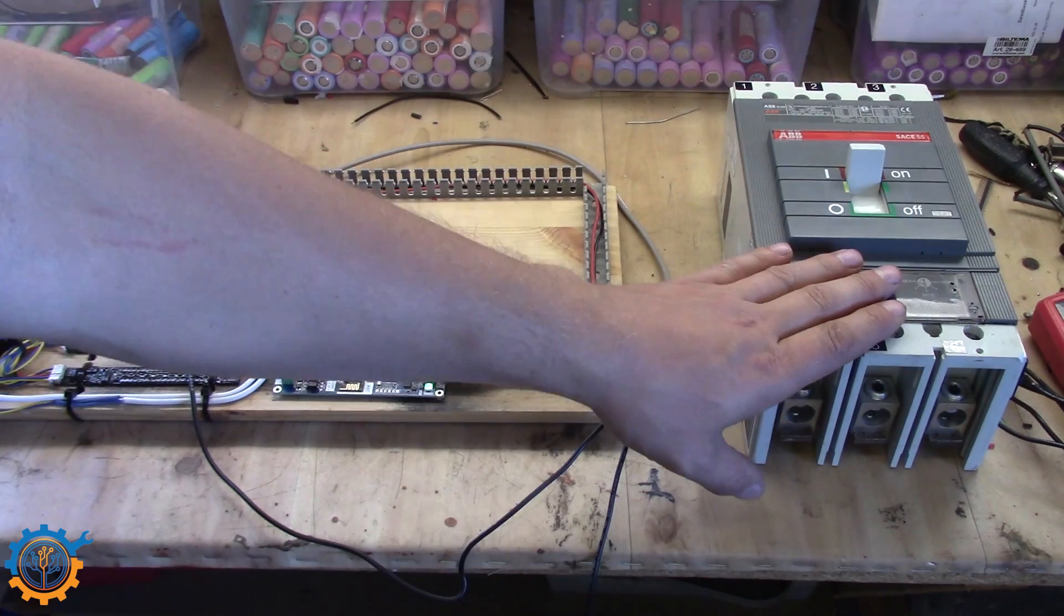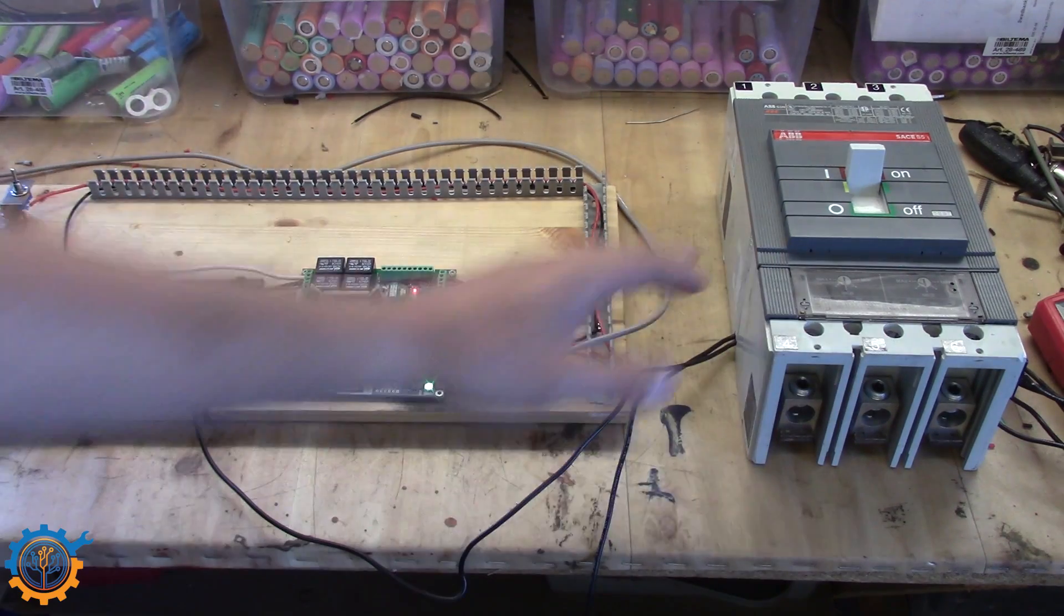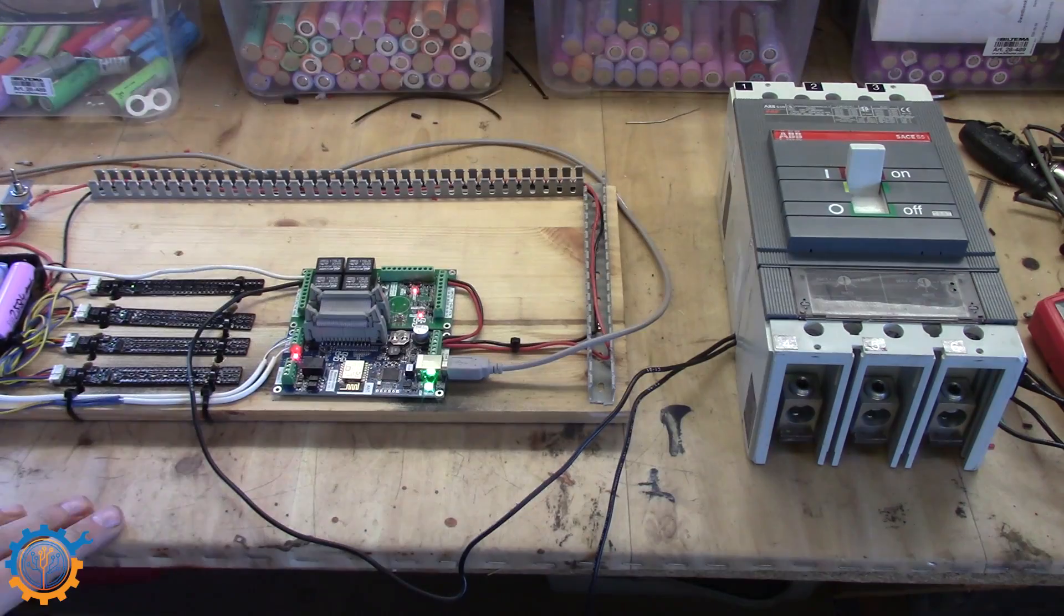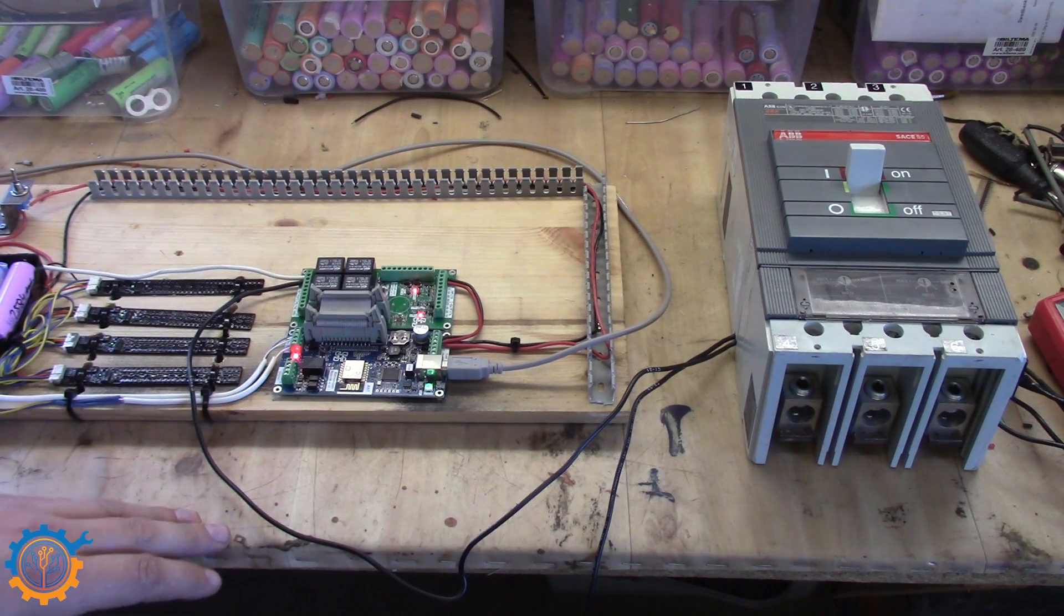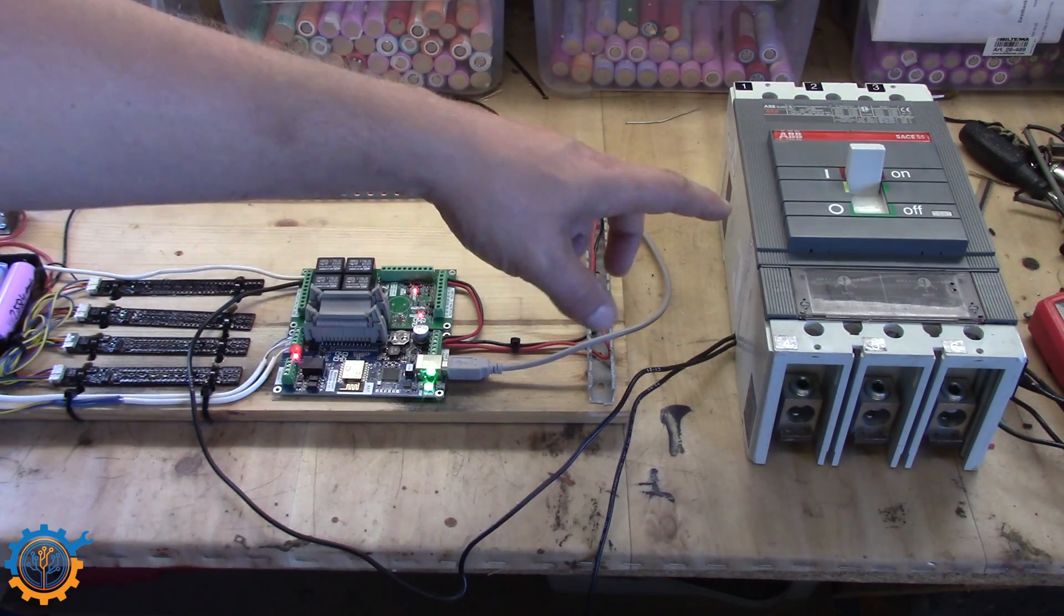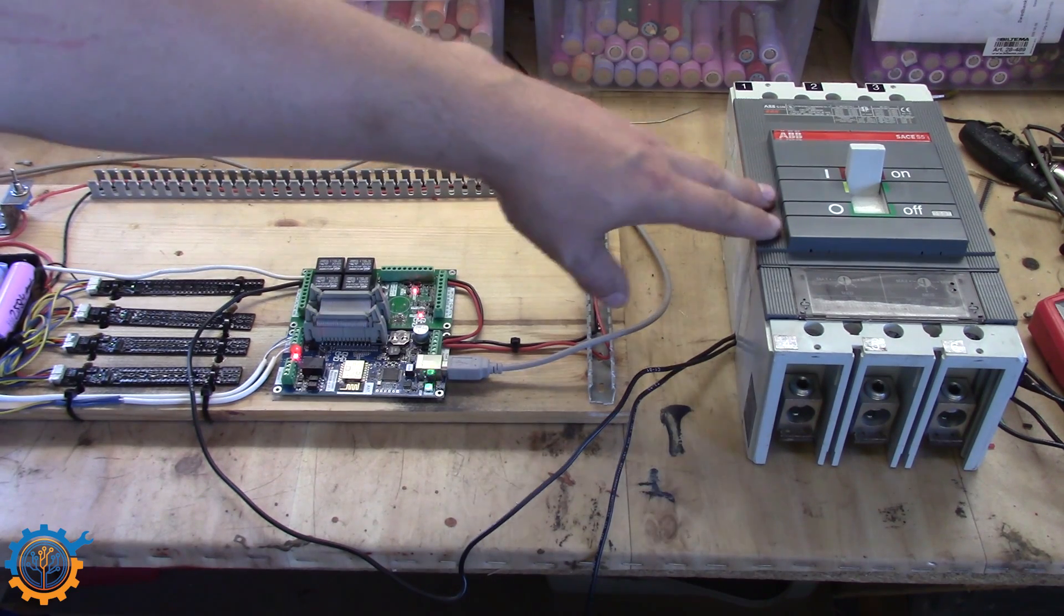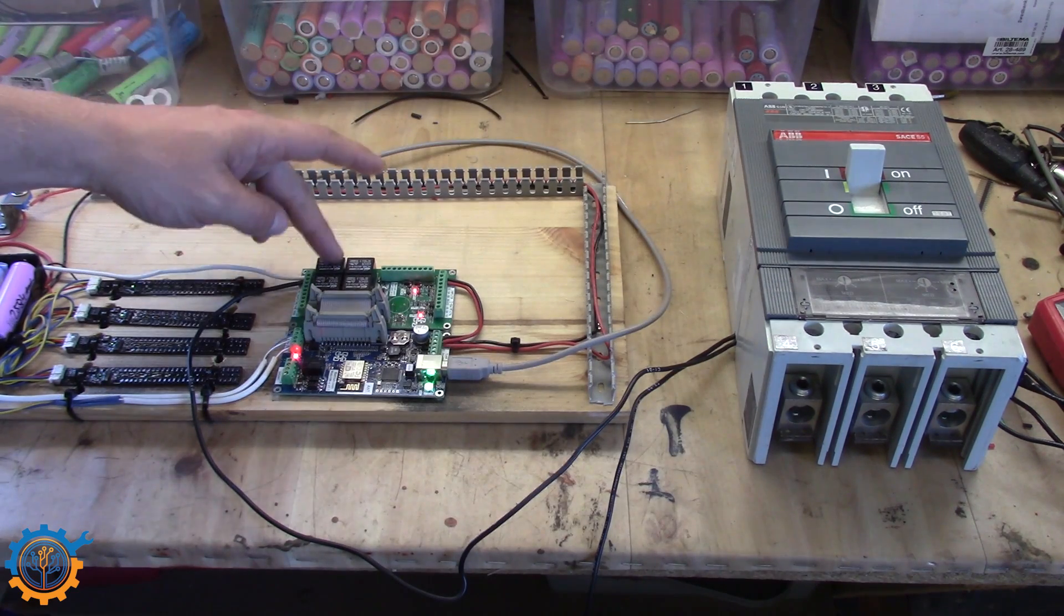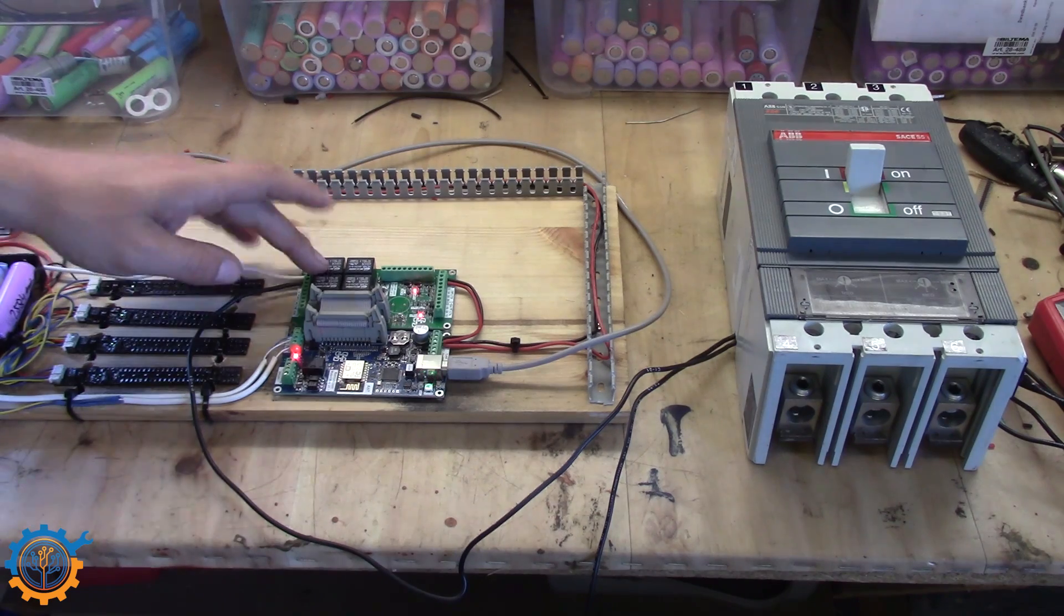It is now time to go back and do a real life test. I have the shunt trip breaker here. It's hooked up. It is in on state. I also have the system hooked up fully here. I have power going to the coil. The only thing protecting or preventing the breaker for tripping is the relay here controlled by the watchmon.